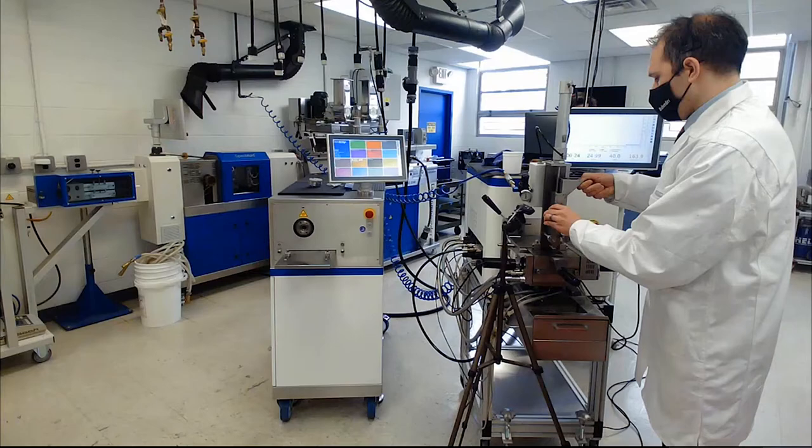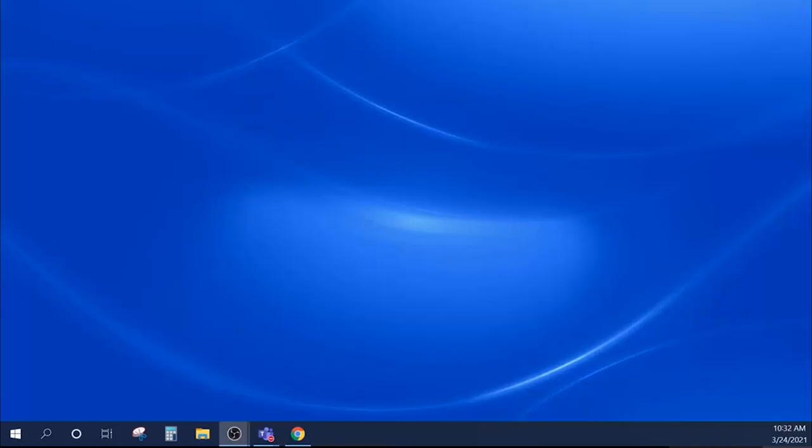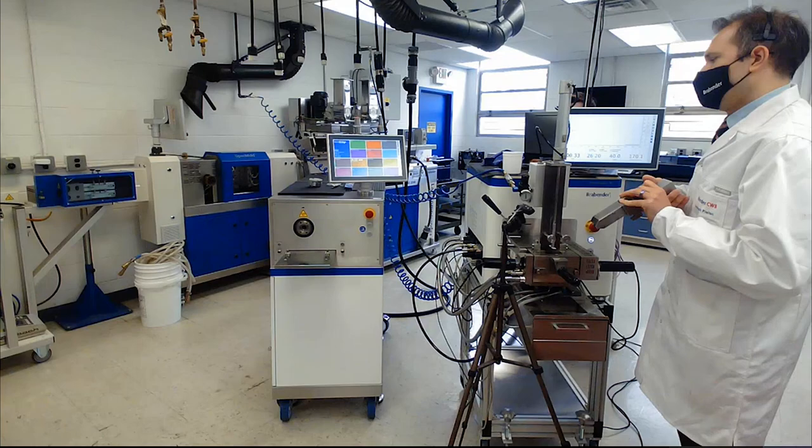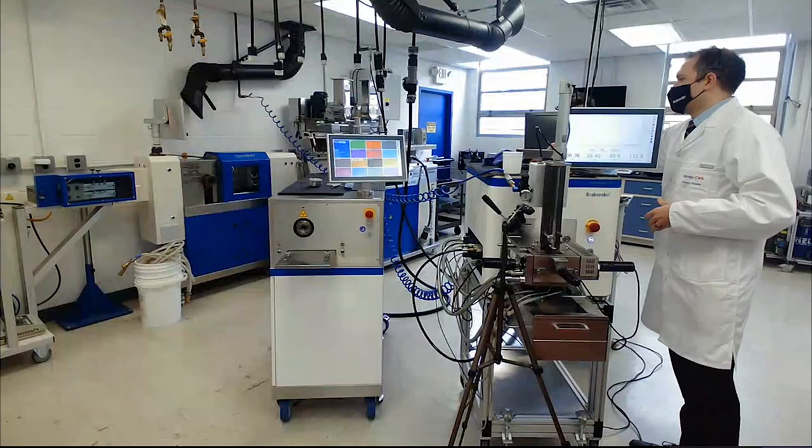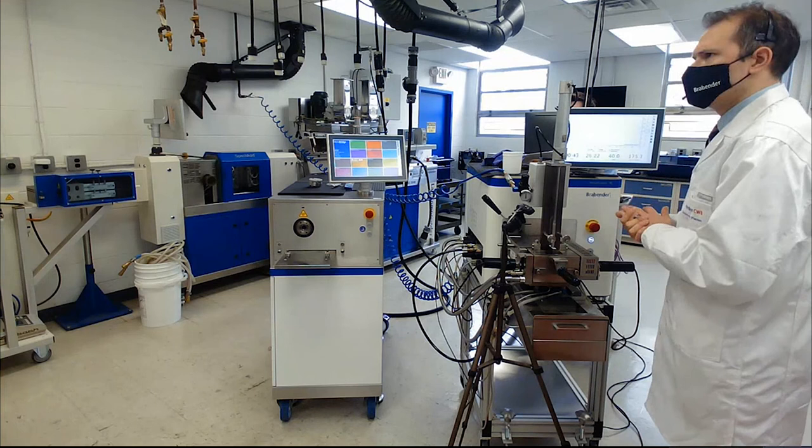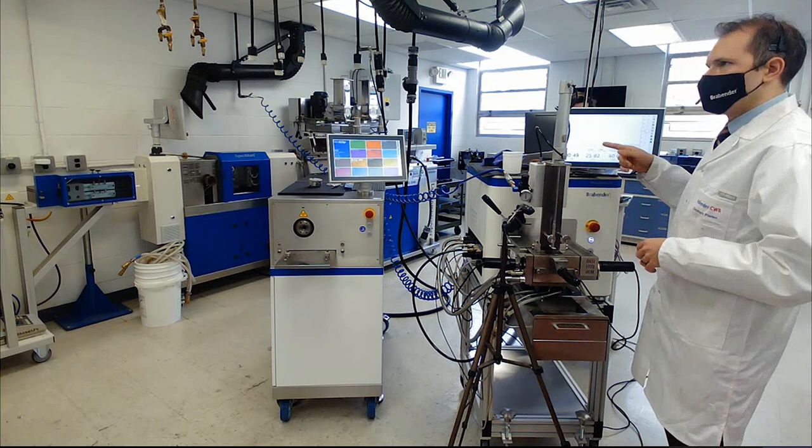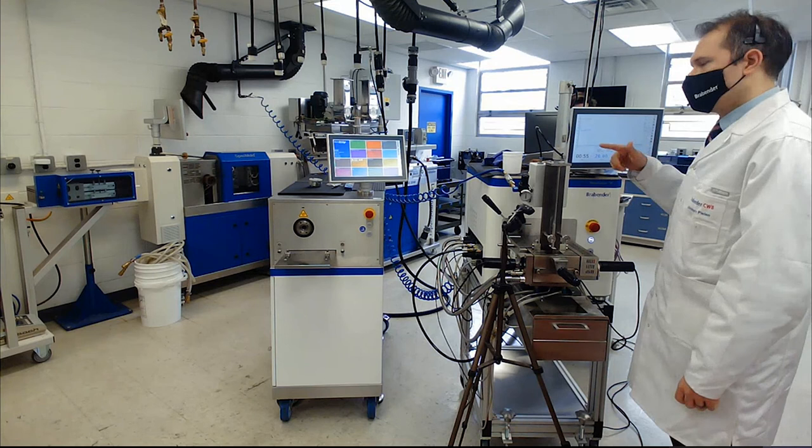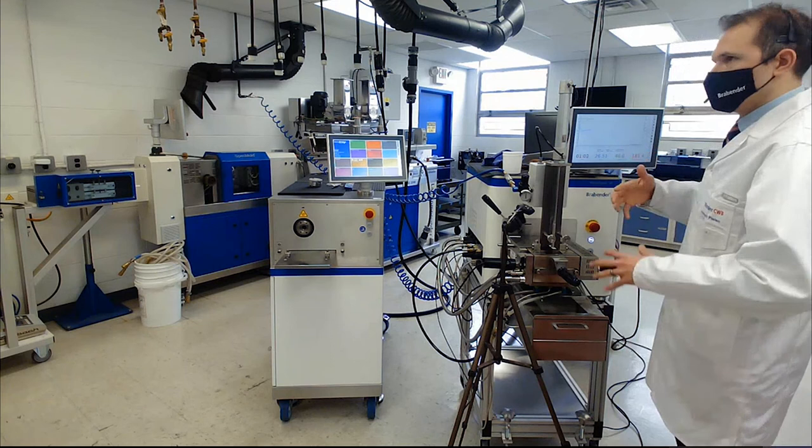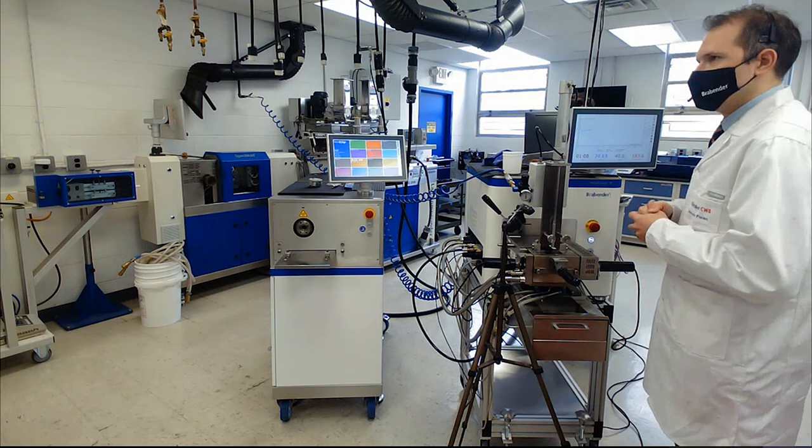I got the prompt to remove the hopper. You will soon see a close-up of how the software looks like. As you can see here, we measure the torque response. We had a loading peak, we had the material melting, and then it was reacting to what's like the fusion happened, so the rearrangement of the PVC molecules trying to build up molecular weight that would result then in heightened secondary torque.